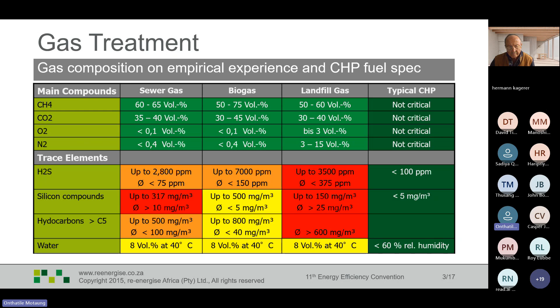I'll go now to the landfill gas. You can see the average H2S is 375, which is much more than what is required by CHP. Silicon compounds are also sometimes greater than 25, while we require less than 5 milligrams per cubic meter. Hydrocarbons greater than 600 milligrams per cubic meter. And the relative humidity required by CHP is less than 60%. So these are the specifications we need to take into consideration when applying gas treatment.